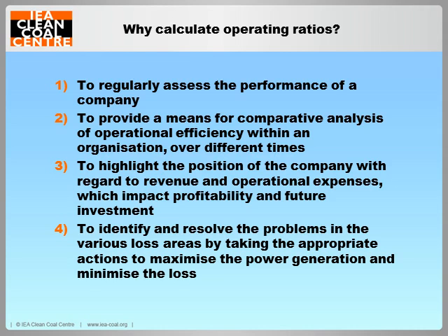Within a power plant, operations are impacted by many factors, including, for example, plant load factor, which is the ratio of the total kilowatt hour actually generated and sold to the total kilowatt hour which the plant can generate if and when it is run at full load. Another indicator is the overall availability factor, considered by some as a better index for comparing plant performance. I won't go into that here. As I said, the report will discuss that in detail.